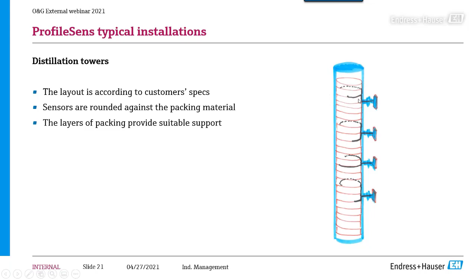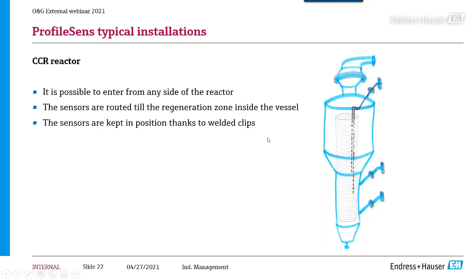If we refer to continuous catalytic reforming, we have something different, because here we have to go inside the reactor and into the regeneration zone, which is inside. And here we need some fixing clips. In other words, there are small metal stripes which get fixed or welded to the internals and keep our thermocouples in position, better when we use the profile sensors of the new innovative thermocouple sensor.